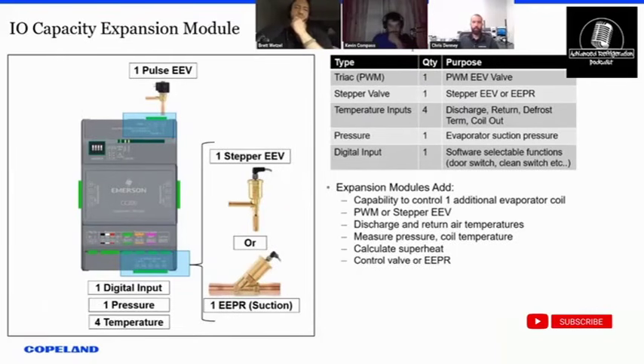Won't take as much time, but the expansion module is our add-on module that is designed to add that additional evaporator coil or to add on that EEPR valve. We're still seeing case OEMs build modular coil case designs. We're still seeing multi-coil unit coolers. And as long as the amperage and electrical design allows it, we can do multi-evap freezers. Depends on how much they want to defrost at one time.